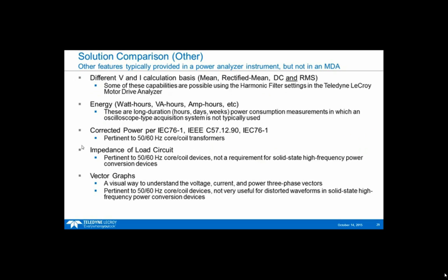And then they also have some historical features that I'd say are really more dedicated for a 50, 60 hertz core coil world, like corrected power, impedance, or vector graphs, things like that. Typically speaking, that's not what you'd use a nice high bandwidth oscilloscope for. You'd usually use our motor drive analyzer for distorted waveform pulse width modulated waveforms that you obtain from solid state high frequency power conversion devices.